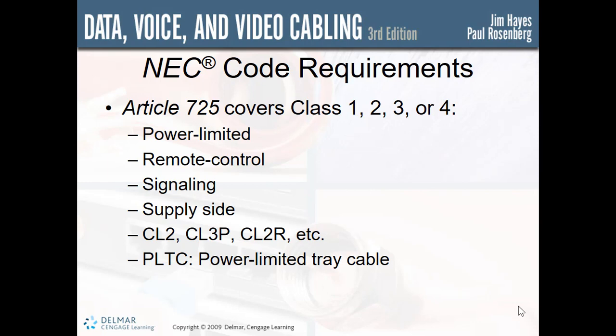Power limited refers to a circuit that has a self-limited power level. That is, whether because of impedance, overcurrent protection, or other power source limitations, these circuits can only operate up to a limited level of power. Remote control and signaling circuits are the Class 1, 2, 3, and 4 circuits that do not have a limited power rating.